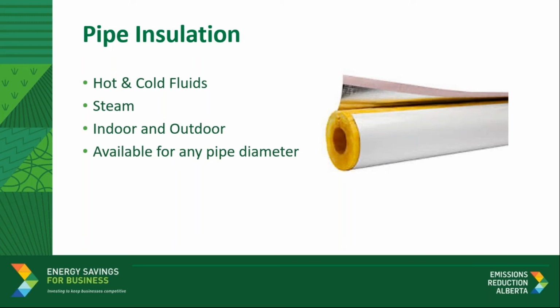Isn't this already a common practice? Yes, absolutely. But the idea here is to encourage participants to improve the existing insulation by adding layers to achieve a minimum R value of 2.5, if they don't have that already. So here's an opportunity to add layers. It is also possible that there are damaged insulation or bare pipes in certain areas. So the ESB program is a good opportunity for businesses to claim incentives and insulate those pipes. Let's go to the eligibility and the requirements on the next slide.